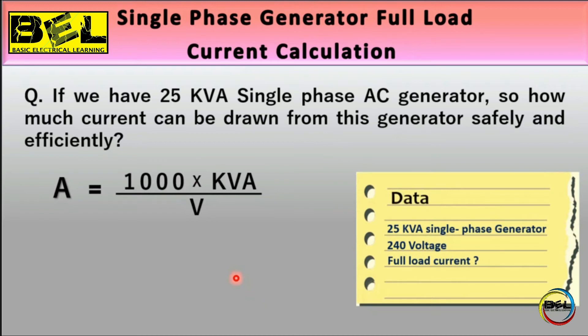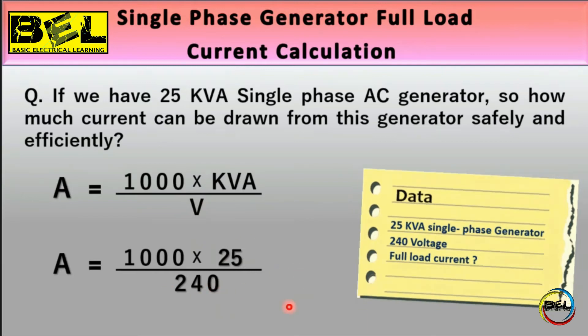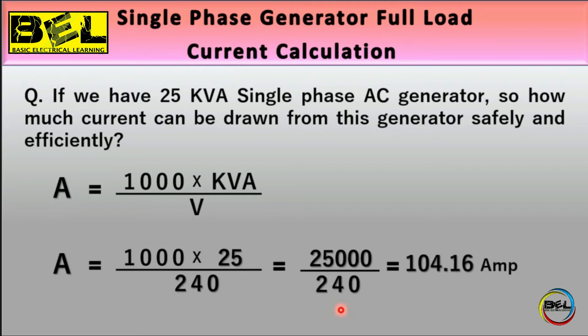Putting in the given data: A = (1000 × 25) / 240, since the generator is 25 kVA and the voltage is 240 V. So that becomes 25,000 divided by 240. Using a calculator, we find the current is 104.16 amperes.